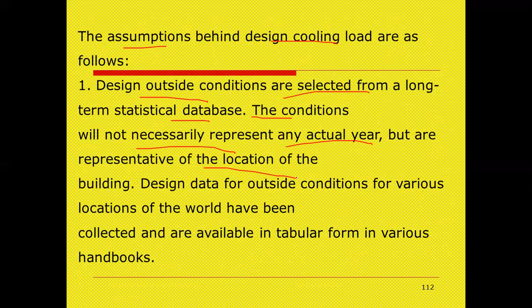Next point. The load on the building due to solar radiation is estimated by clear sky conditions. The building occupancy is assumed to be the full design capacity. So whatever the design you are doing for the building, the occupancy is assumed to be the full design capacity. All building equipment and appliances are considered to be operating at reasonably representative capacity.